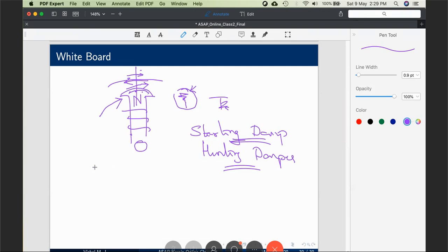You sense the speed, you extract the frequency component from that, and use that as the frequency to the stator. For example, consider a 50 hertz machine. 230 volt is the phase voltage. Now the rotor is rotating at some speed, correspondingly 20 hertz. Which means this will be your stator frequency as well. Now, what is the ratio K? It is 0.4, that is 20 by 50. Now, what voltage must you apply? 0.4 into 230. How much will that be? 23 into 4, 92 volt. I'm not sure, let it be 92 volt.